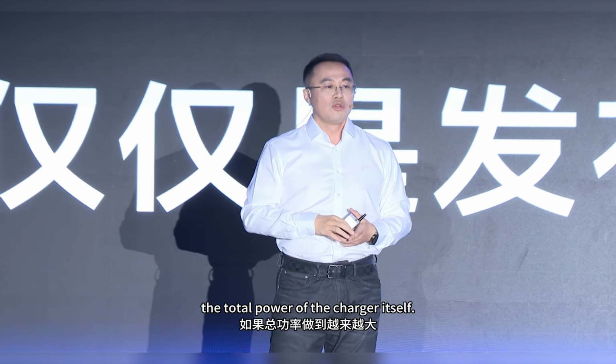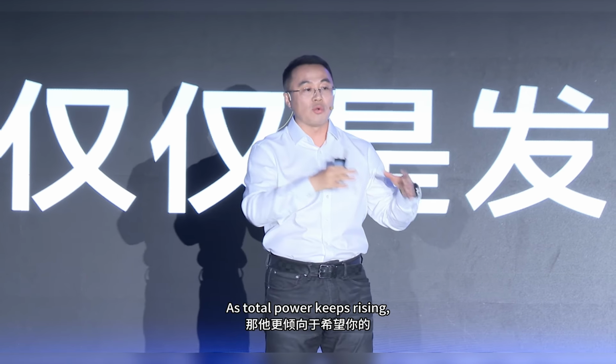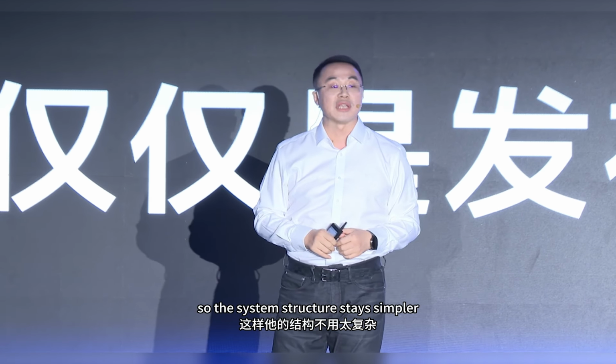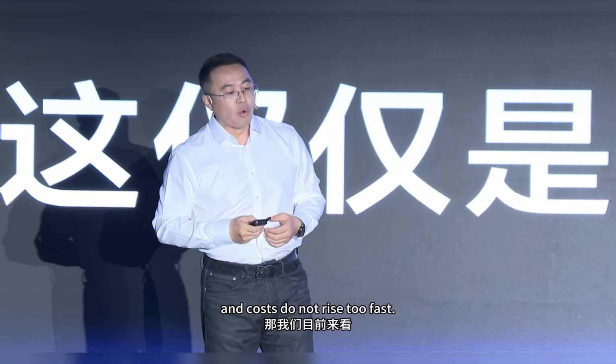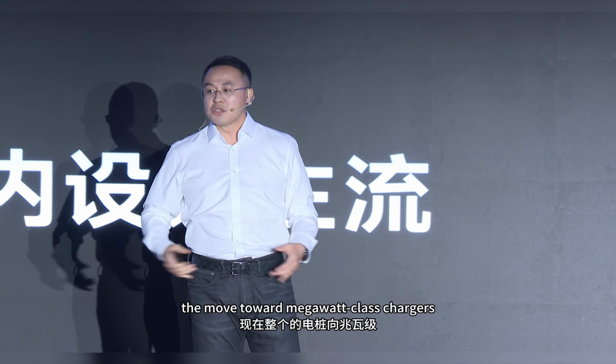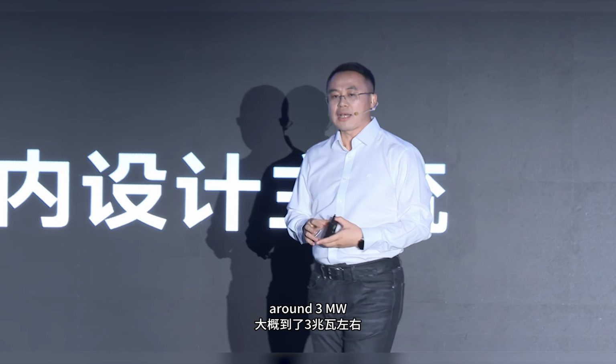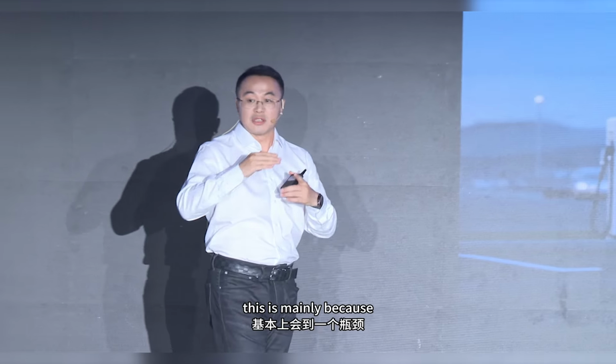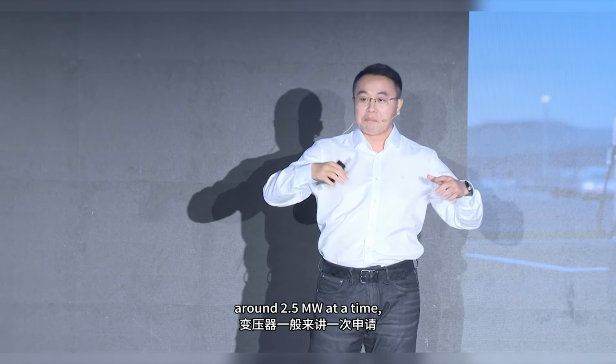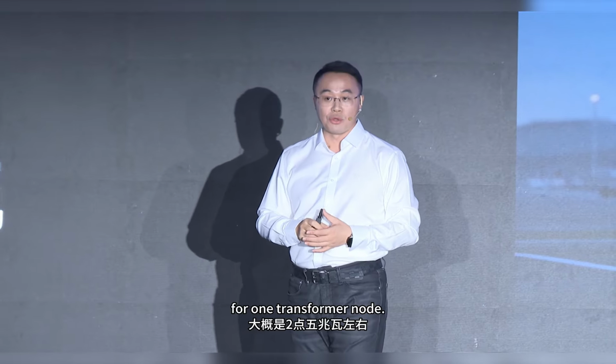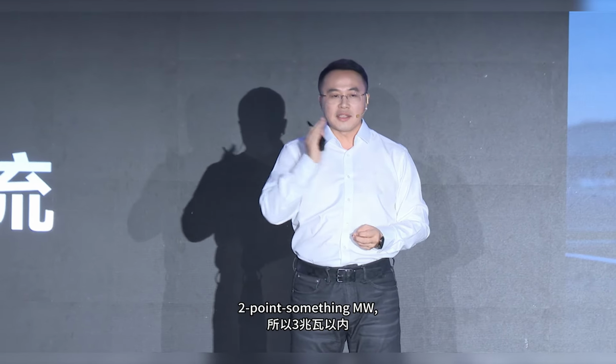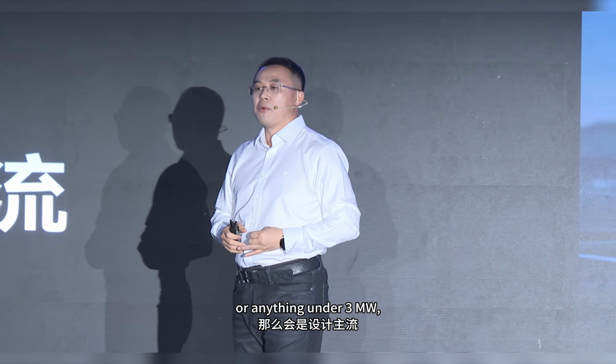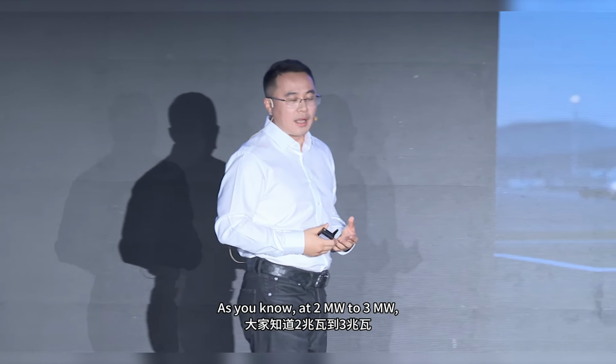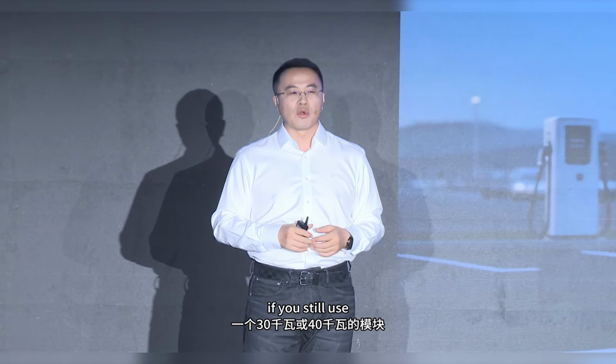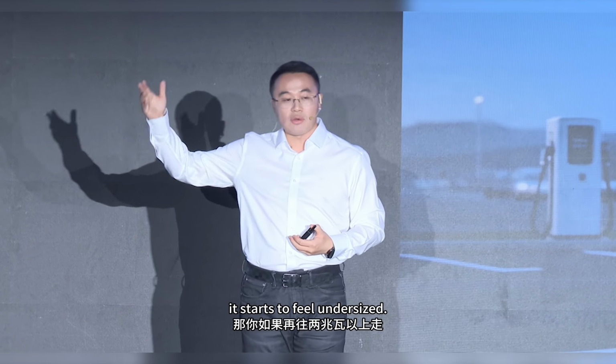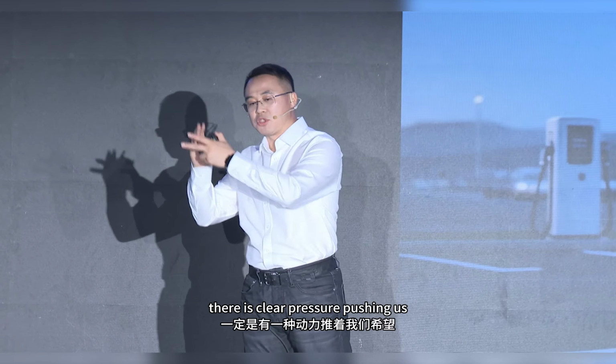One is the total power of the charger itself. As total power keeps rising, the market naturally wants higher power modules too, so the system structure stays simpler and costs do not rise too fast. From what we see now, the move toward megawatt class chargers is very clear, but in that process, around 3 megawatts, you start to hit a bottleneck. This is mainly because a transformer application is usually around 2.5 megawatts at a time for one transformer node. So below 3 megawatts, whether 1 megawatt, 2 point something MW, or anything under 3 megawatts, these will be the mainstream design range. As you know, at 2 megawatts, 3 megawatts, if you still use a 30 kilowatts or 40 kilowatts module, it starts to feel undersized.